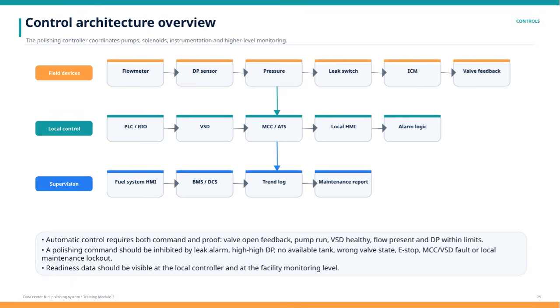Local control is managed through PLCs or RIOs, variable speed drives, motor control centers with automatic transfer switches, and local HMIs. These elements handle the immediate control actions and feedback, ensuring the system operates efficiently on a day-to-day basis. On the supervision side, we have the fuel system HMI, building management or distributed control systems, trend logging, and maintenance report functions. These tools give operators a comprehensive view of system status and help with diagnostics and performance tracking.